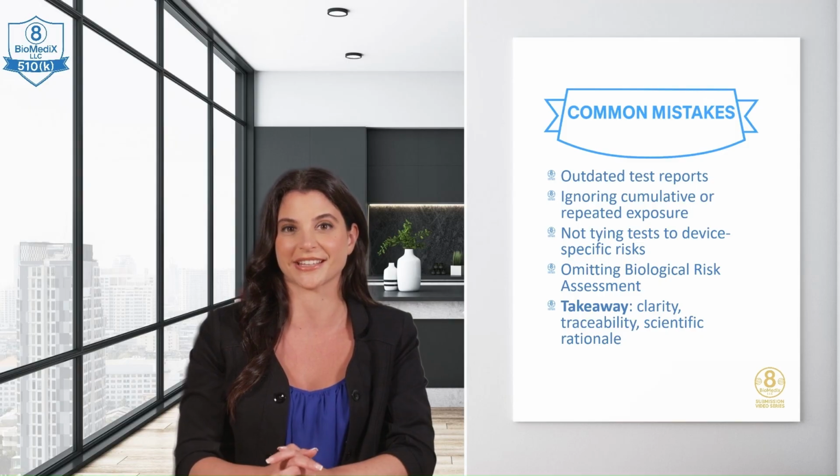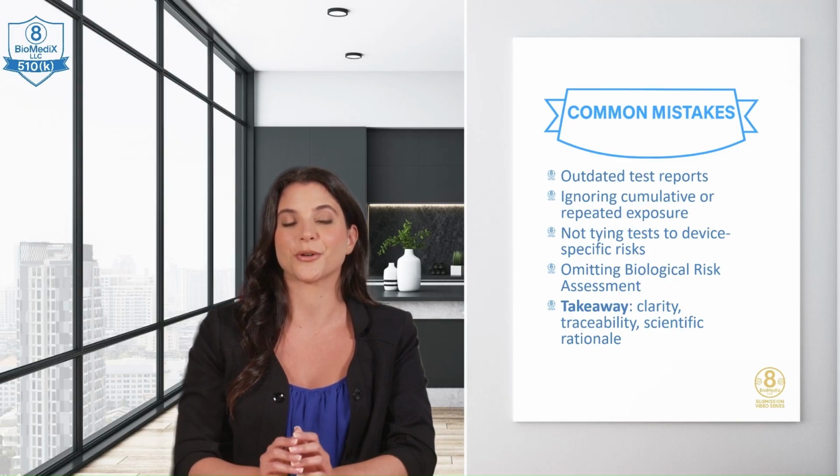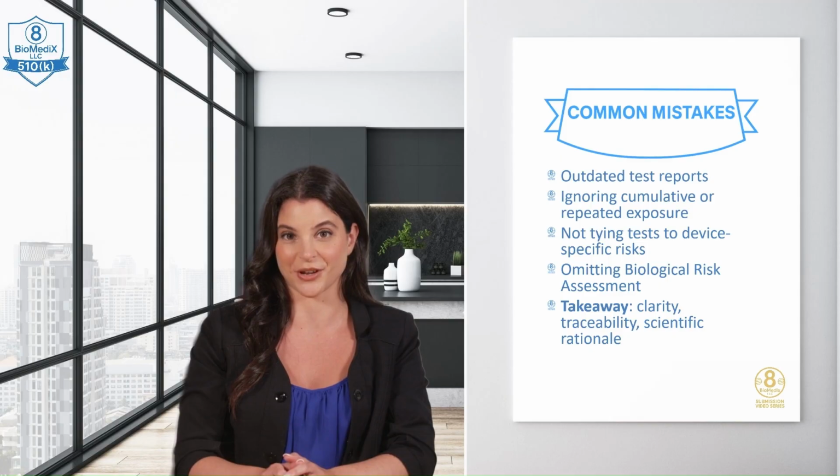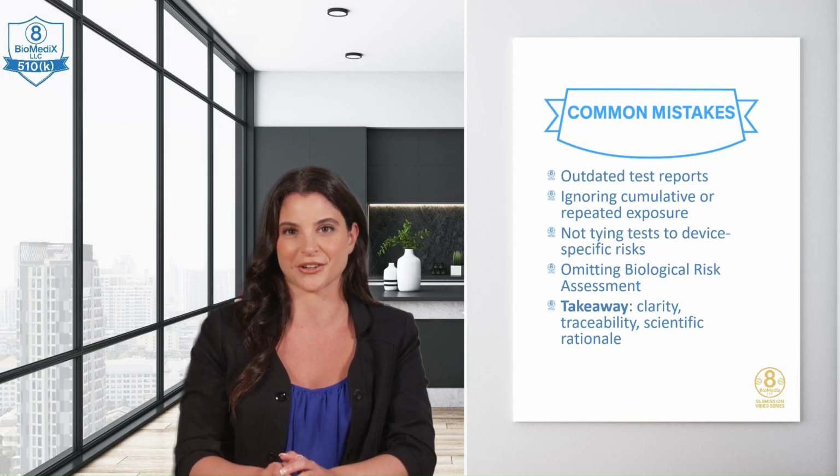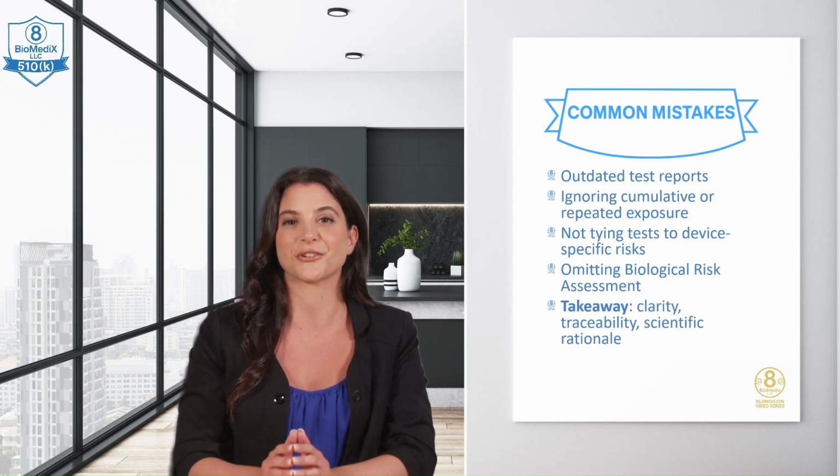Common mistakes and key takeaways. Let's quickly cover some common mistakes to avoid. First, using outdated test reports that don't reflect the final sterilized product. Second, ignoring long-term or repeated exposure risks. Third, failing to tie each test back to your device's materials, use case, or contact conditions. And perhaps the most common, skipping the biological risk assessment. This is required by both ISO 10993-1 and the FDA. This could trigger a hold.